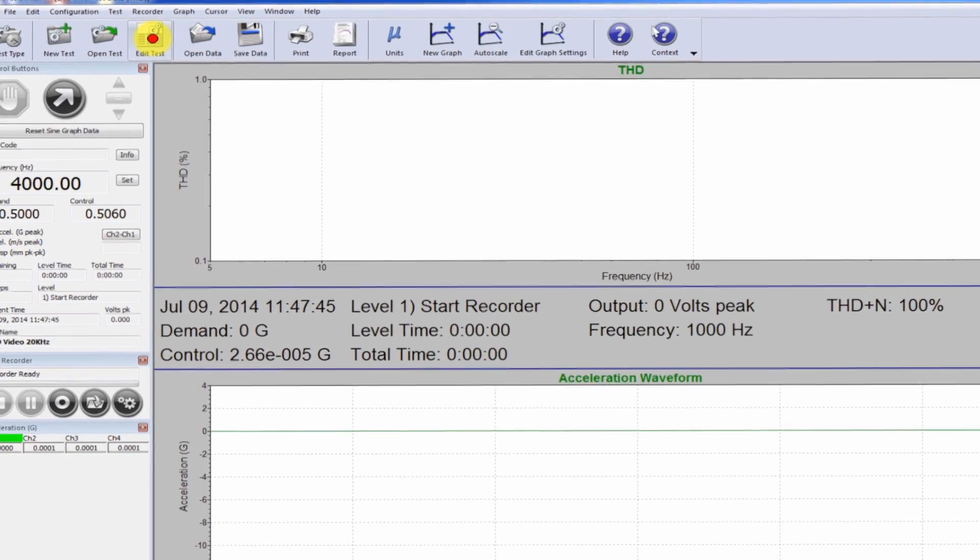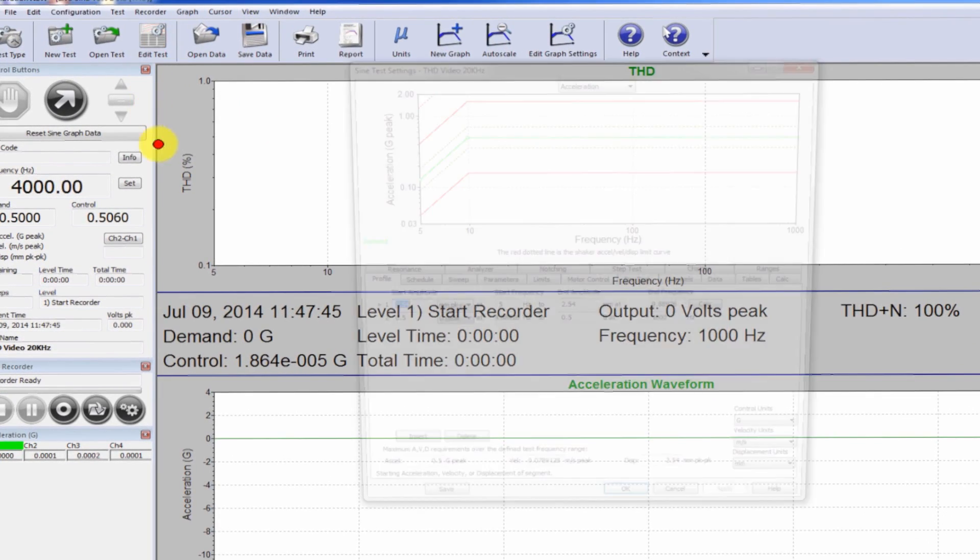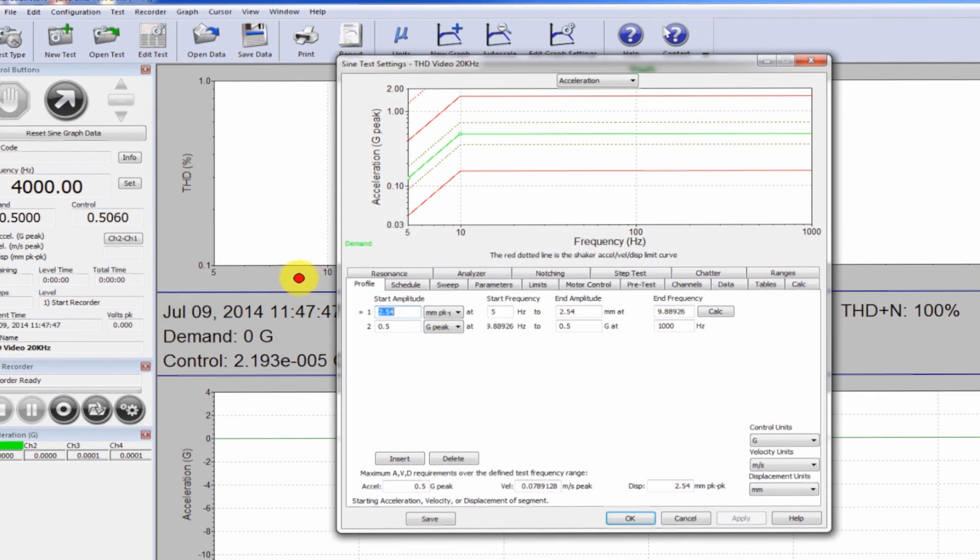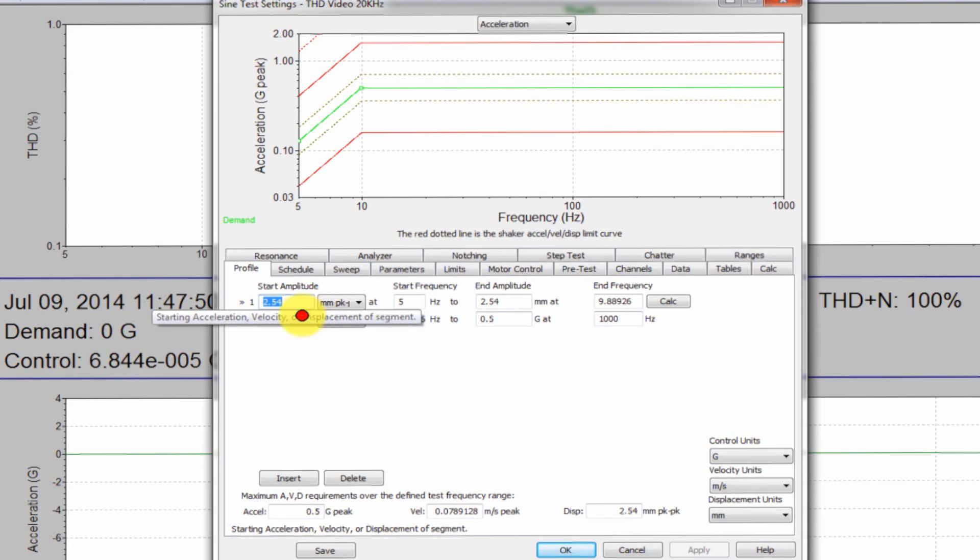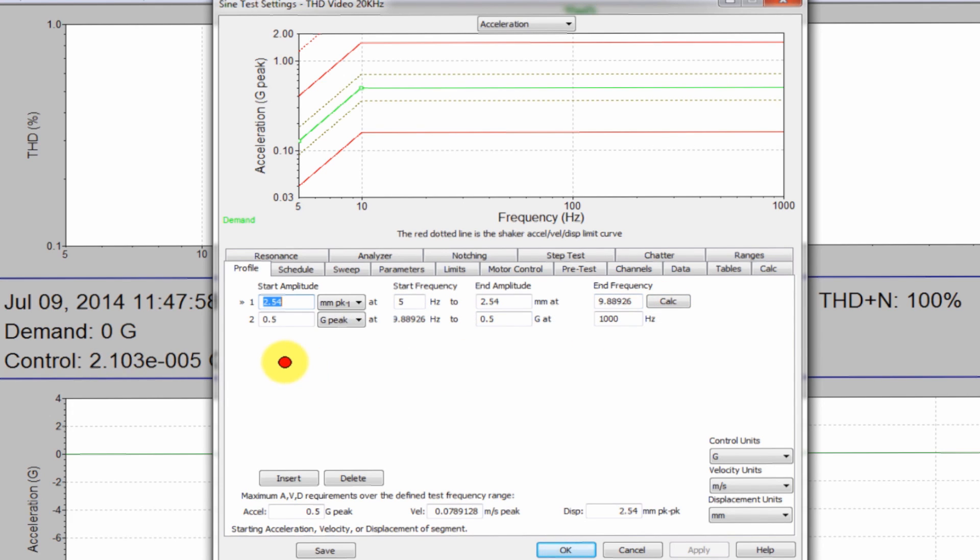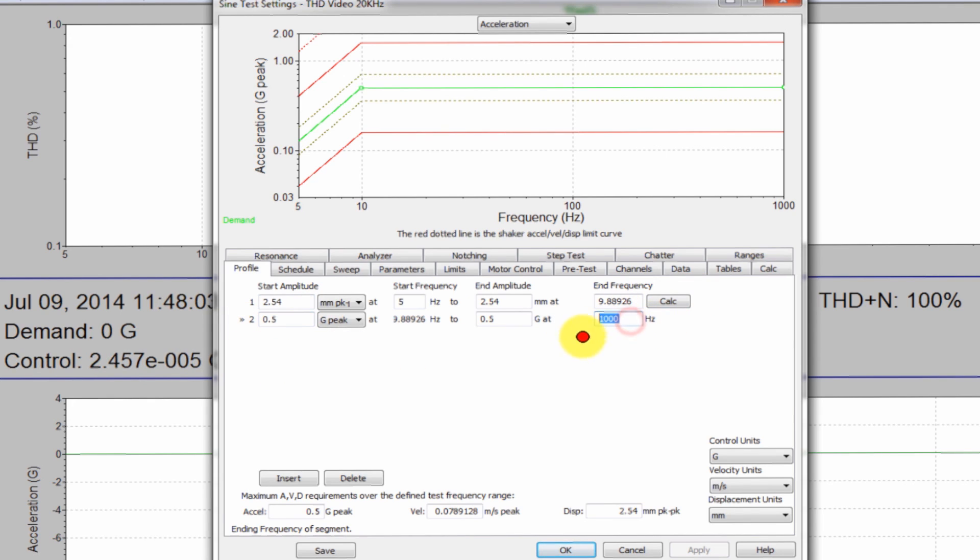So I've already configured a sine sweep test to calculate THD. If I go to my edit test, you can see what I've done. I'm running at 0.1 inch or 2.54 millimeters, starting at 5 hertz, up to about 10 hertz, which is that crossover frequency for 0.5 G, and then I'm running that up to 1000 hertz. I'll show you why I stopped at 1000 hertz for this test in just a moment.